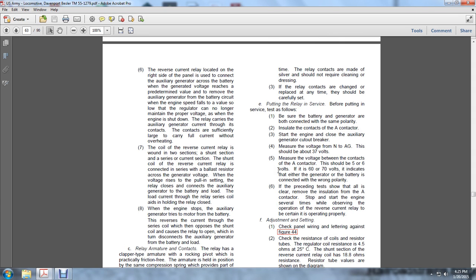Putting the relay in service. Before putting the relay into service, test as follows. Be sure the battery and the generator are both connected with the same polarity. Insulate the contacts of the A contactor. Start the engine, close the auxiliary generator cutout breaker, and measure the voltage from N to AG. This should be about 37 volts. Measure the voltage between the contacts of the A contactor. This should be 5 to 6 volts. If 60 to 70 volts is indicated, either the generator or the battery is connected with the wrong polarity.